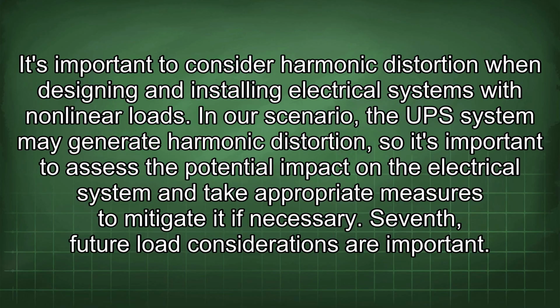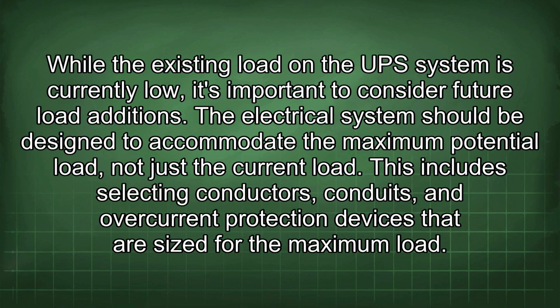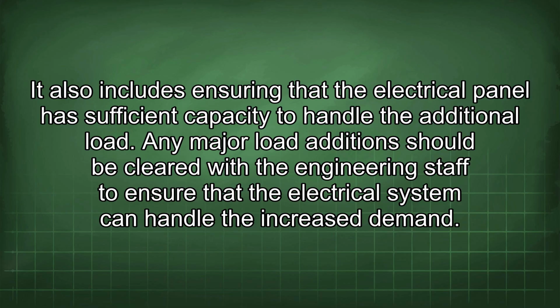Seventh, future load considerations are important. While the existing load on the UPS system is currently low, it's important to consider future load additions. The electrical system should be designed to accommodate the maximum potential load, not just the current load. This includes selecting conductors, conduits, and overcurrent protection devices that are sized for the maximum load. It also includes ensuring that the electrical panel has sufficient capacity to handle the additional load.